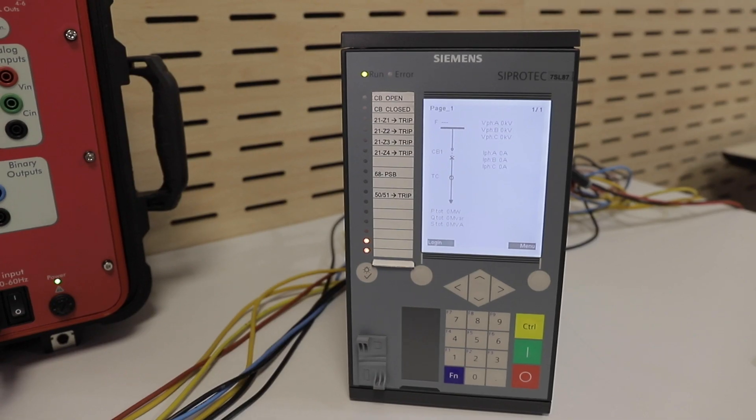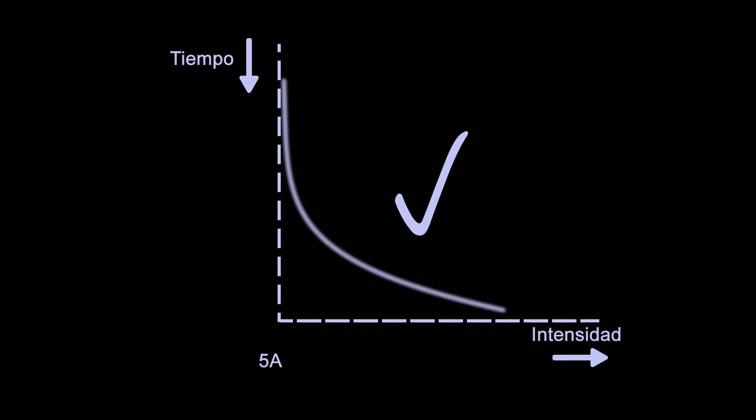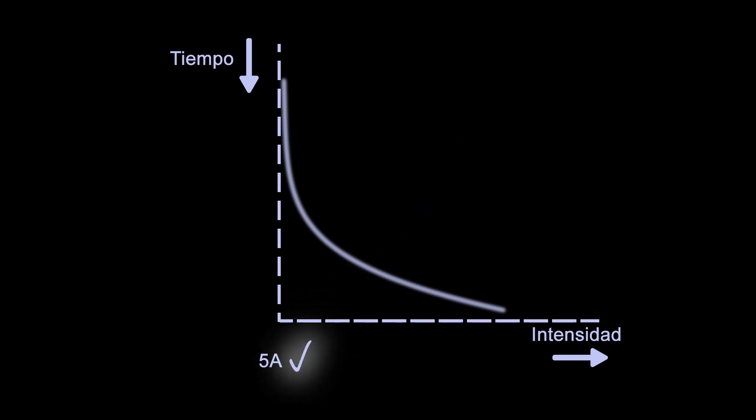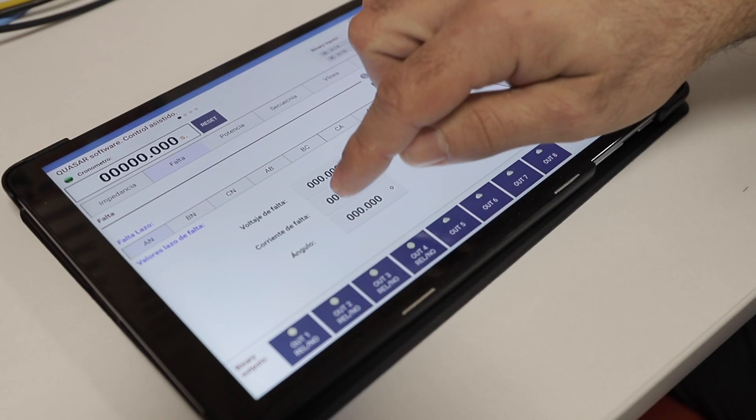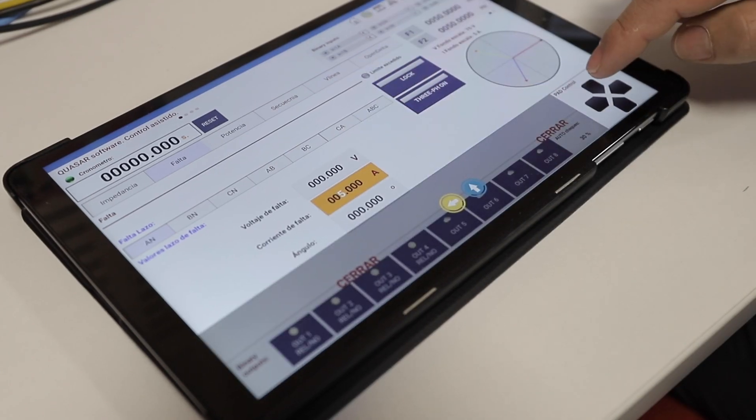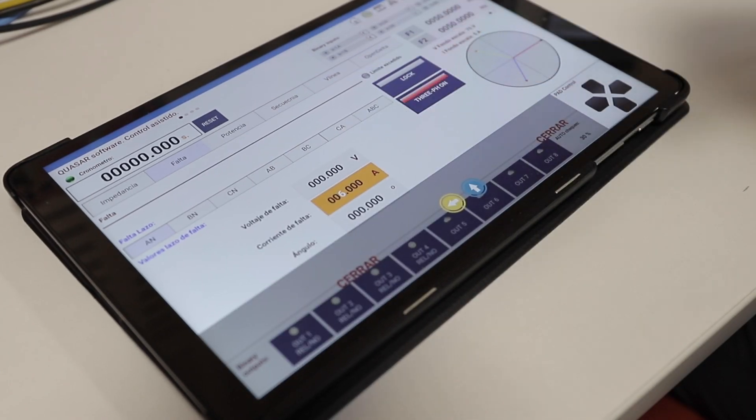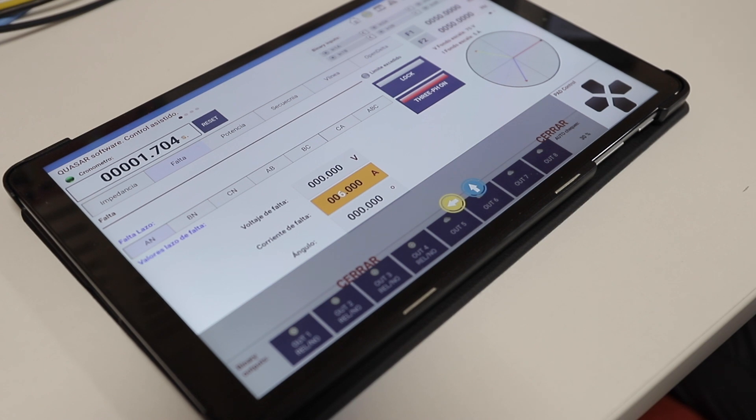The current in our first test is too small, so the relay won't evaluate it as a fault and will never operate, thus passing the no operation test successfully. The current in our second test does fall inside the operation zone of the curve, so the relay should operate this time.